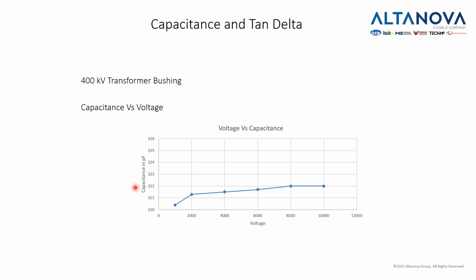So all the polarization is done with 12 kilovolts. If we change the voltage and do the so-called tip up or tip down test, which is often performed on rotary machines, our capacitance needs to stay the same. So actually it is. We see that the only difference is that here the capacitance is 320.5 and here it is 322. So there is, excuse me, a very small change in the capacitance.